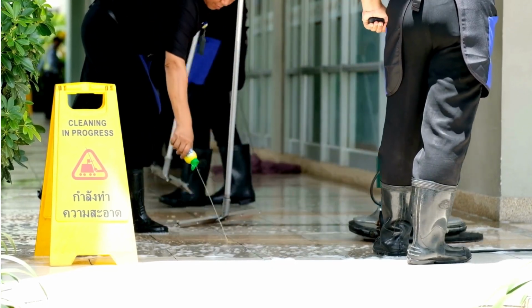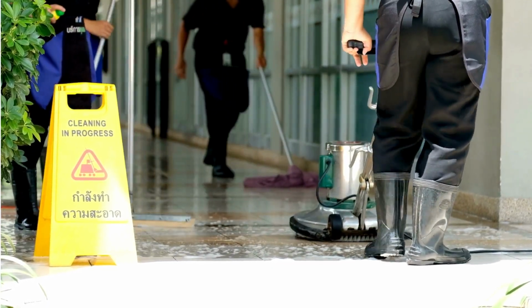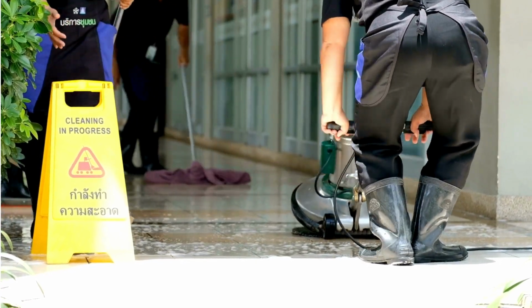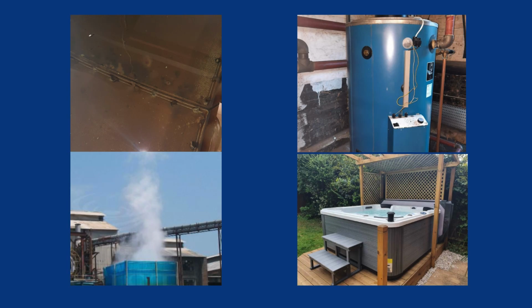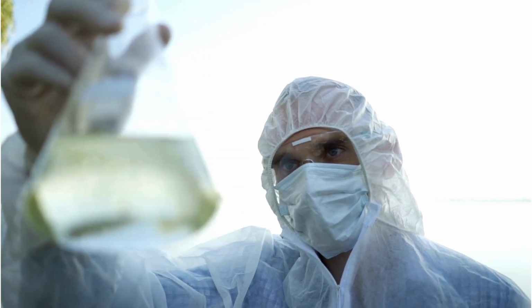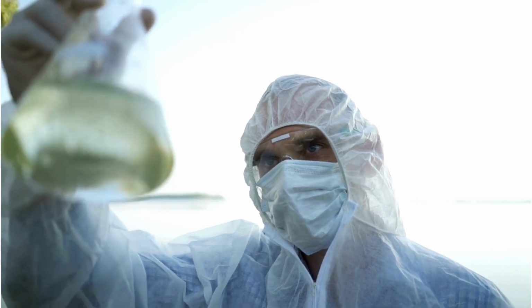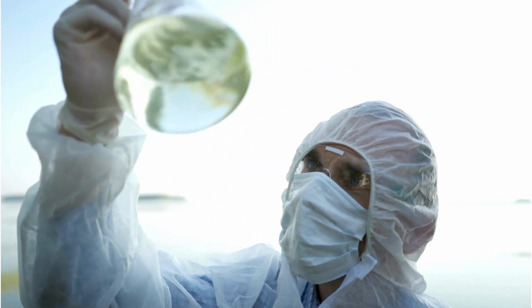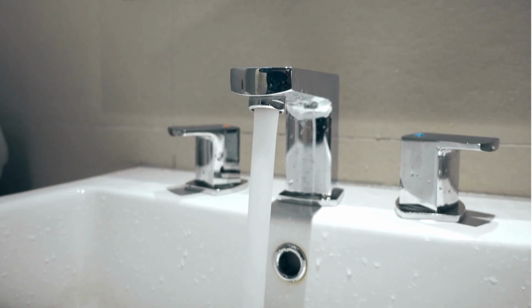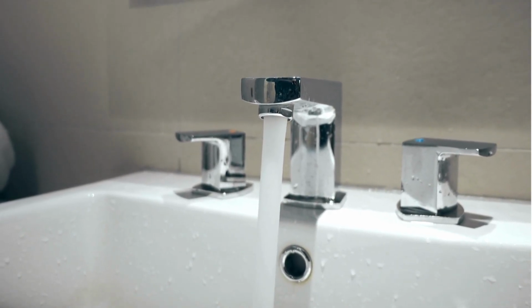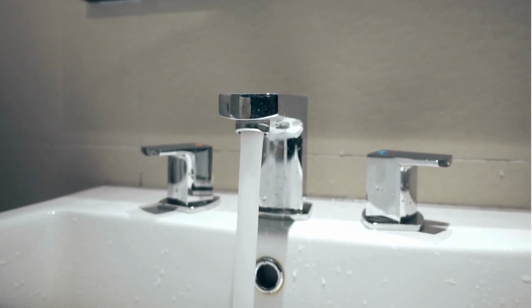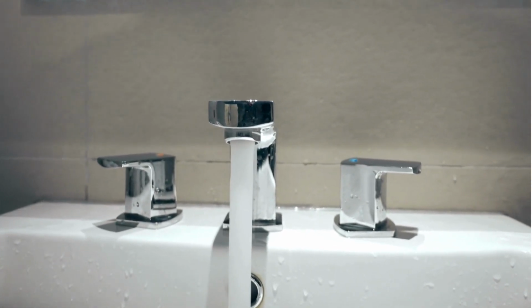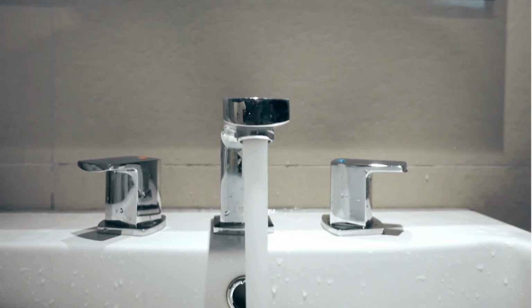The risk of Legionella can be reduced by properly maintaining and cleaning areas where the bacteria can grow, such as cold water storage tanks, water heaters, cooling towers, and hot tubs. Regular testing for Legionella can also be done to ensure that levels are within safe limits. The temperature required to kill Legionella is at least 60 degrees Celsius, which is why it is important to ensure that hot water systems are properly maintained and set to the appropriate temperature.